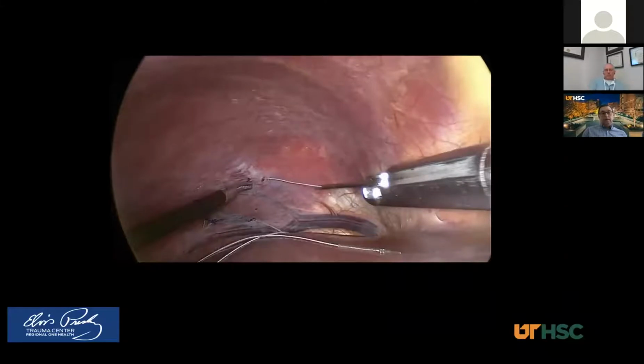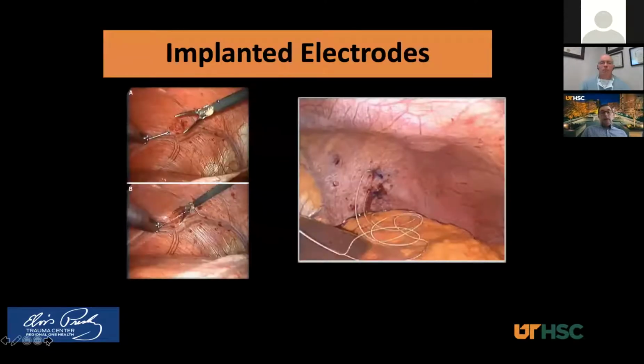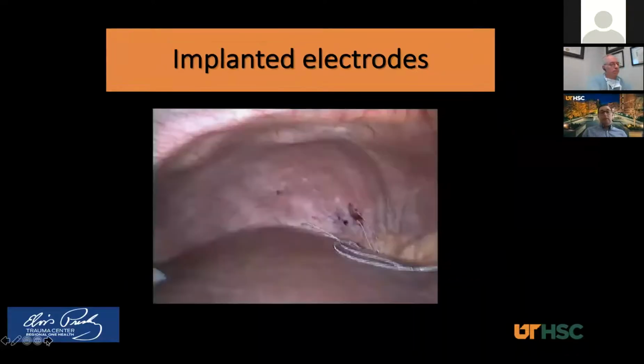And now you'll see there's 2 electrodes implanted in the right side of the diaphragm there. It's kind of what the picture would look like here. On the right, you'll see, I think this is actually from one of Ray's manuscripts, 2 electrodes implanted in the left side of the diaphragm. Again, there's the left lobe of the liver there, omentum, and the anterior electrode, posterior electrode. There's a lot of excess wire that's left inside of the abdomen to ensure we have enough to tunnel through the subcutaneous tissue and out to be able to connect to the external pulse generator.